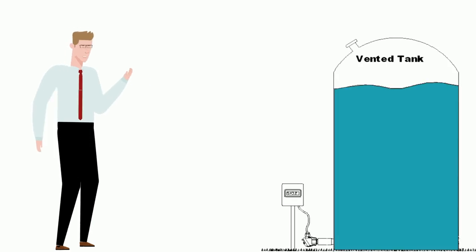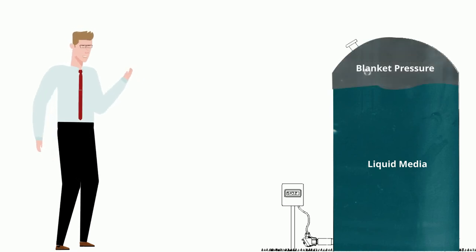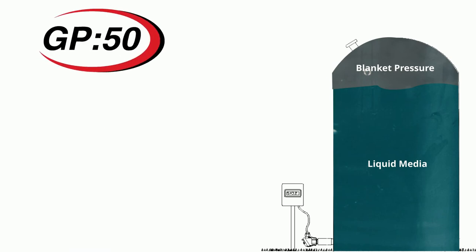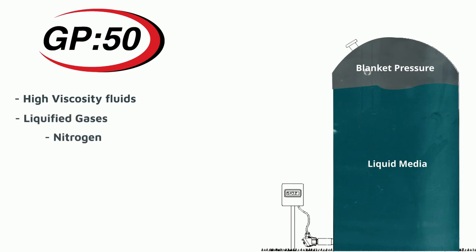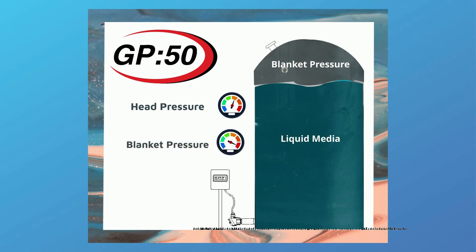At times the level in a pressurized tank is also required. A pressurized tank is used where the fluid has a blanket of air, nitrogen, or other gas on top of the liquid level. This blanket pressure may be used to help assist high viscosity fluids out of the tank, or used in liquefied gases such as nitrogen, oxygen, or other gases that create a high pressure blanket when in a liquid state. In order to determine the level in a pressurized tank with a hydrostatic type transmitter, a differential measurement is required. The sealed pressurized tank will exert a head pressure due to the depth of the fluid as well as add the blanket pressure that is on top of the liquid.